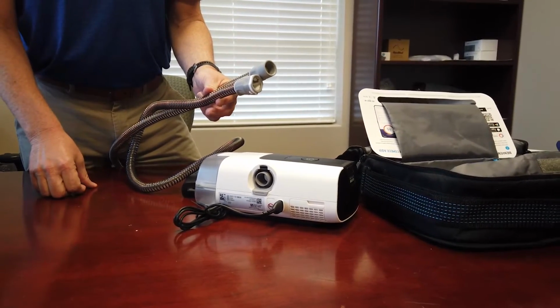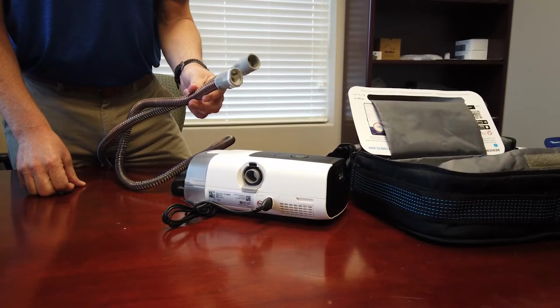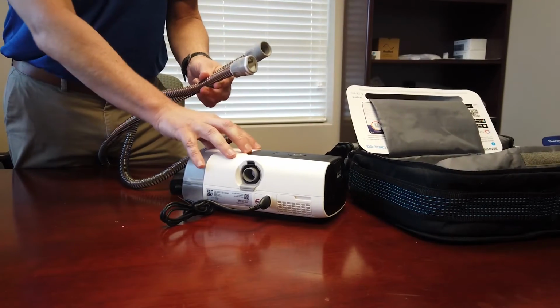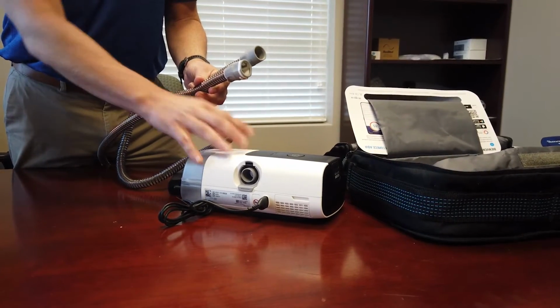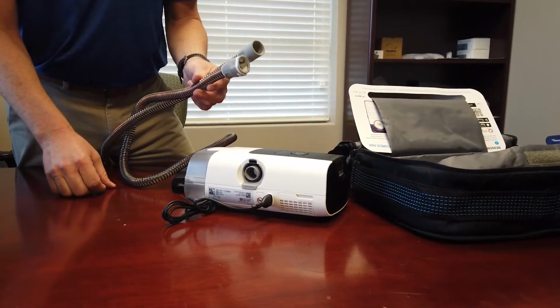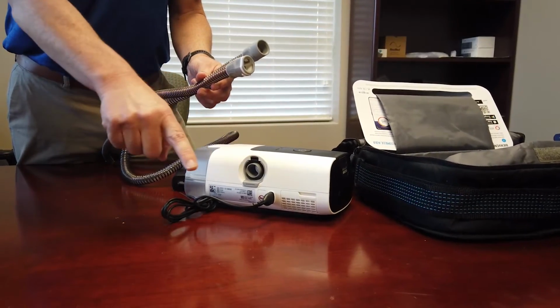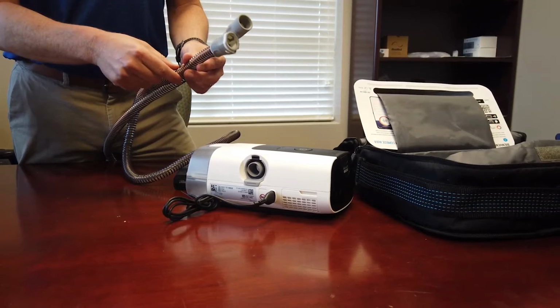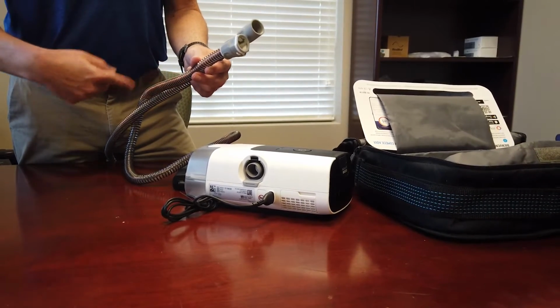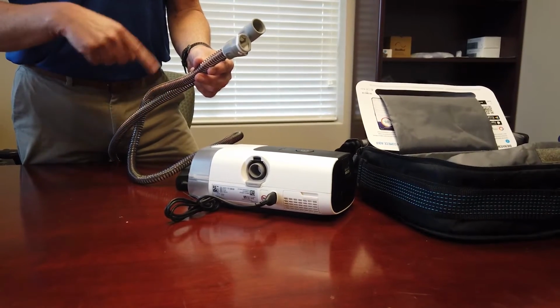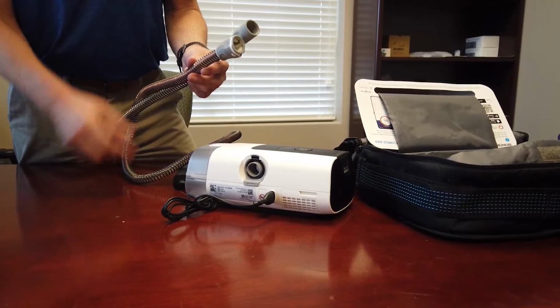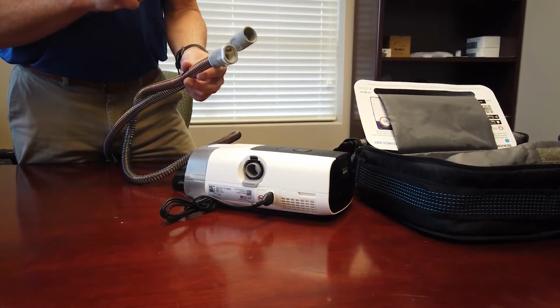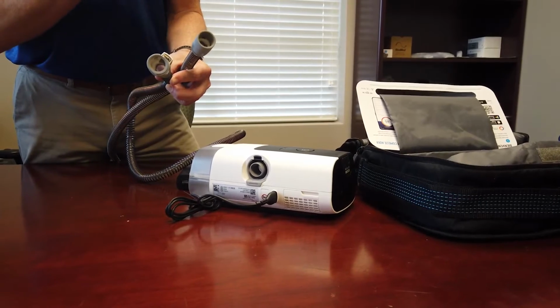Anytime you're using a humidifier with a CPAP machine, one problem that you can run into is the humidifier is heating up the water and the air to produce that moisture to prevent dryness. But once that air passes into the tubing, if it ends up cooling down too much once it's inside of there, then you're going to end up with condensation. So if you ever notice moisture inside the tubing, that's going to be why. The heated tubing is specifically designed to prevent that. So that's why it does have this special adapter.